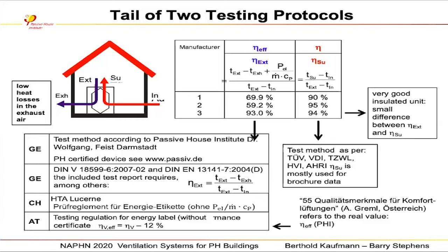Passive House measures, as shown there by the blue arrow, the outgoing airstream, and basically they're measuring how much energy is lost from the building. This is very easy. We can determine the temperature of that leaving air, and we can tell you how much energy is embodied in that. It's basically 1.08 BTUs per cubic foot per delta T of Fahrenheit temperature. So if that air is leaving at 10 degrees warmer than it is outside, then it's 10 times 1.08 times the volume of air. If it's 500 CFM, it's 500 times 10 times 1.08. It's a lot of BTUs.